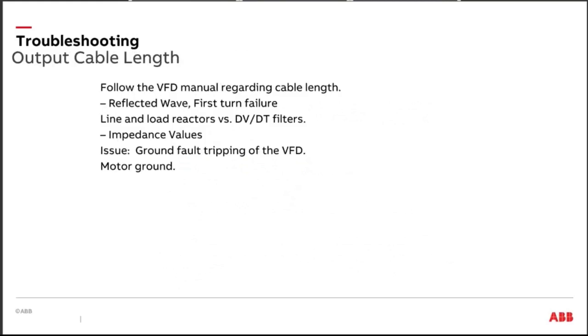Your output cable length, you need to look and see what your manufacturer says about that. In general, I tell my little guys, my 10 horsepowers and below or 20 horsepowers, I want you to be well under 100 foot, about 75 foot. Okay, don't put 300-400 foot on a little bitty drive. That could be very problematic. When we get into bigger drives, we can have some longer distances.